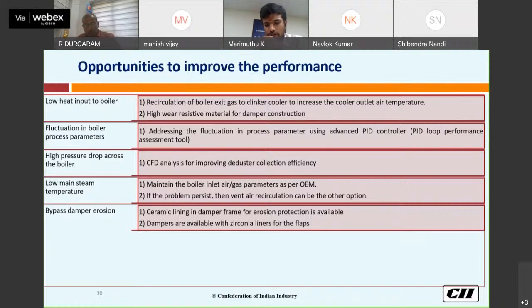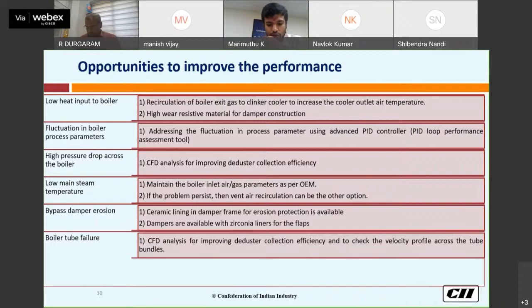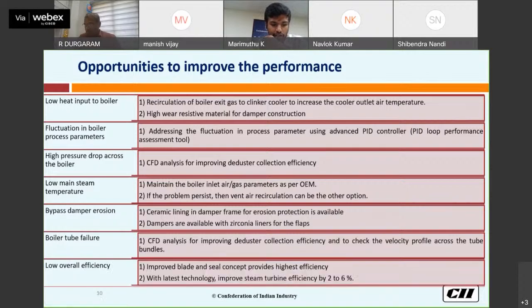So that also we can use. And boiler tube failure. As we discussed, the cause will be due to the uneven gas distribution. So for that we can go for CFD analysis if we are having frequent failure. This is mainly applicable from the erosion point of view. And another one is low overall efficiency.